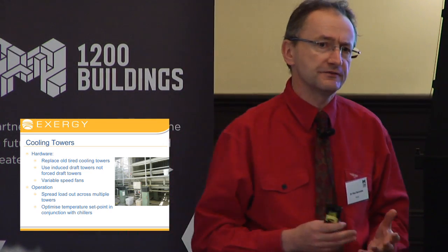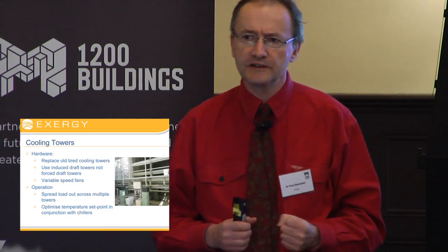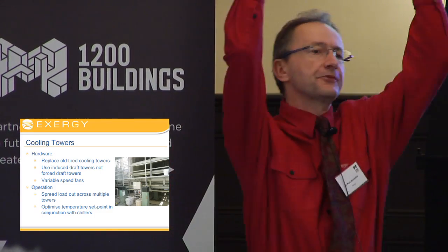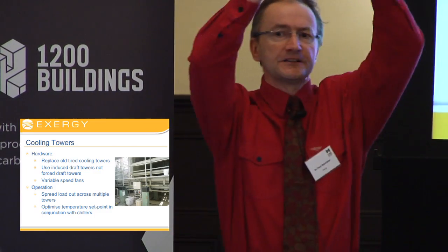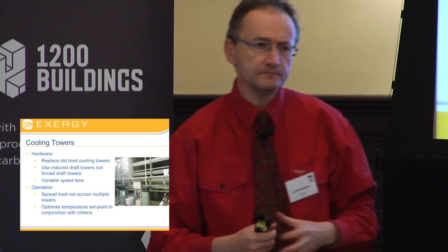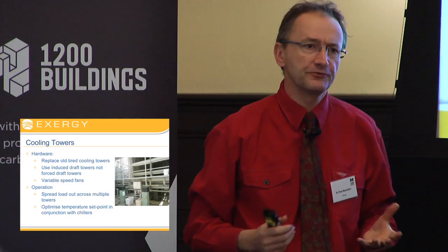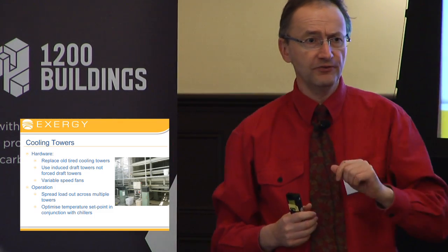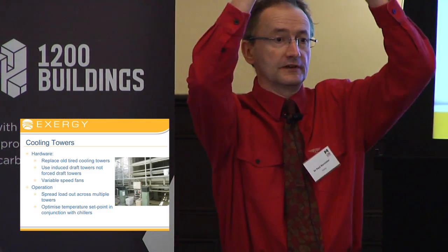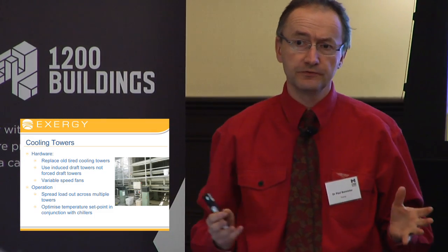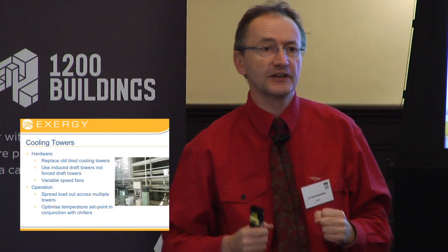There are different types of cooling towers: induced draft and forced draft. Forced draft towers have a fan at the bottom that pushes air up through them. Induced draft towers have a fan at the top that sucks air through. Induced draft towers are generally more efficient, simply because when you turn the fan off, air can still move through the tower. Whereas with forced draft, because the fan sits in the airflow, you can't get any air through when it's off, so you get no free cooling. You have to run the fan to make the cooling tower work, which makes it inherently less efficient.